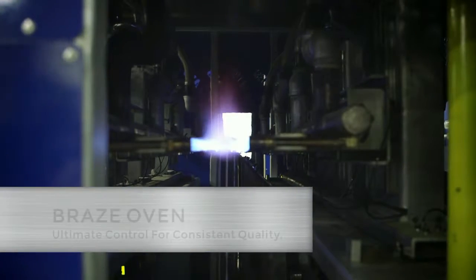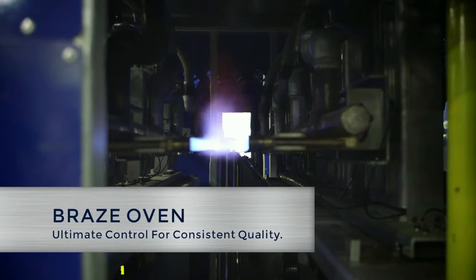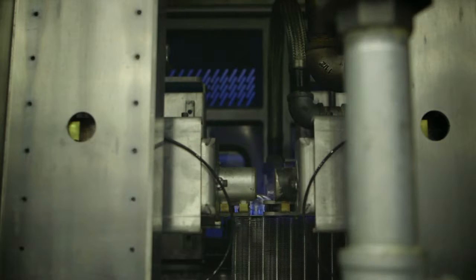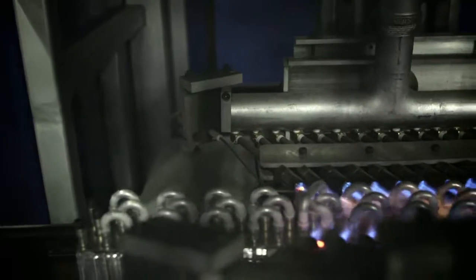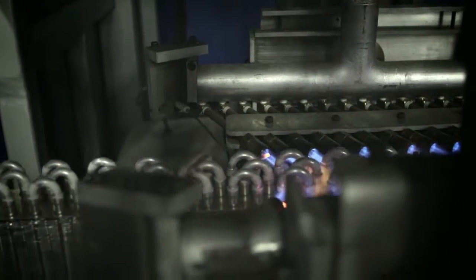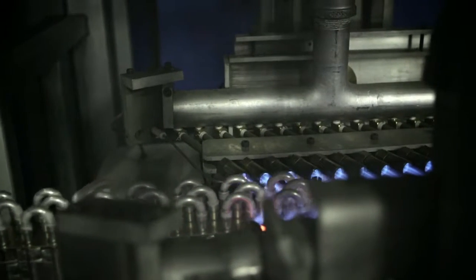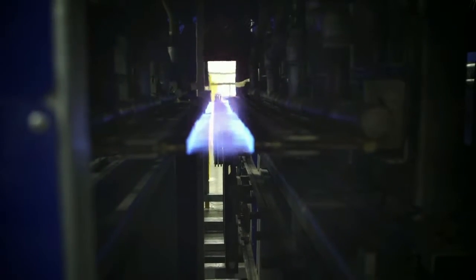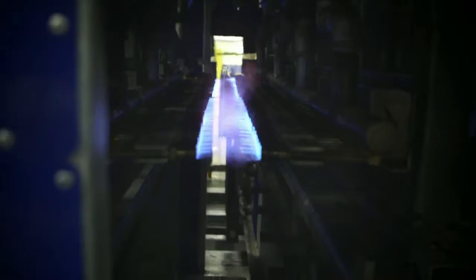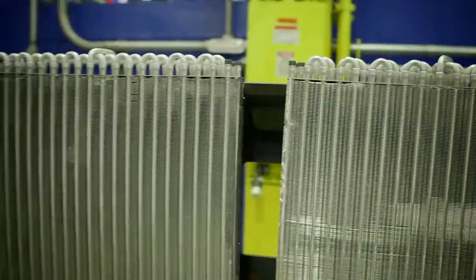Brazing aluminum is uniquely different from other alloys in that the temperature window between the alloy and the base metal is less than 100 degrees, requiring close control of brazing temperature for an effective joint. Our special braze oven has temperature data feedback and 4 unique zones to accurately control penetration of the alloy in the braze joint, creating a consistent joint for years of leak-free operation in the field.